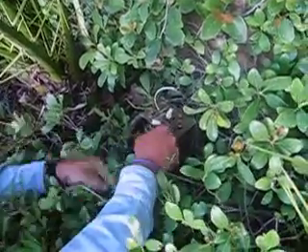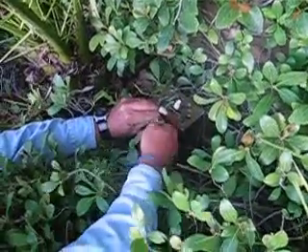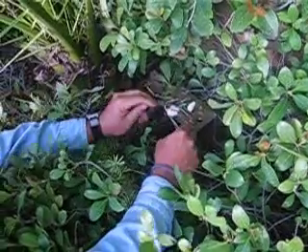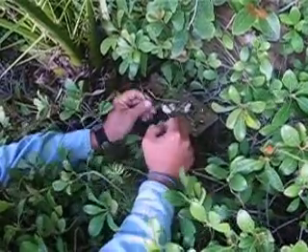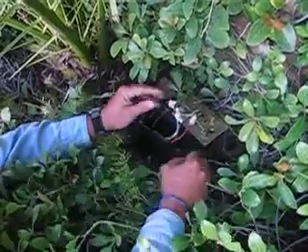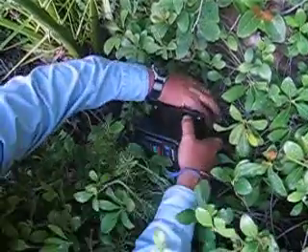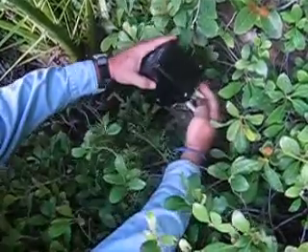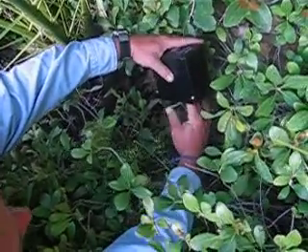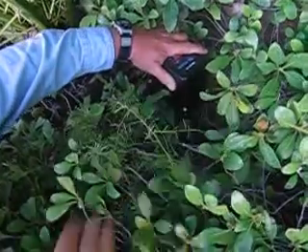The next part we're going to do are the two line wires coming in. We're going to hook up the white neutral wire, and then the black wire is going to go to the switch leg that comes from the switch breaker. Once you get all that done, you're going to tuck the wires back in here, get those screws lined up, and then you're going to have a working GFI for your pool light. It's going to be that simple.